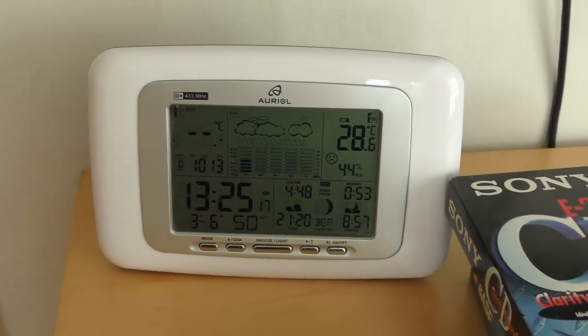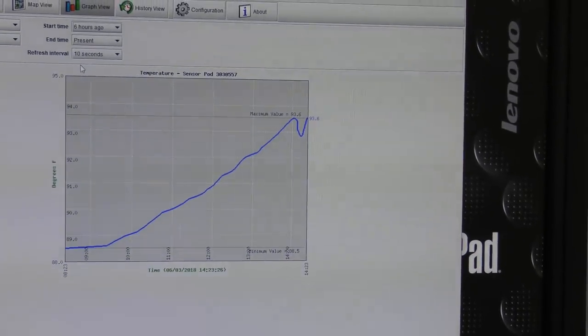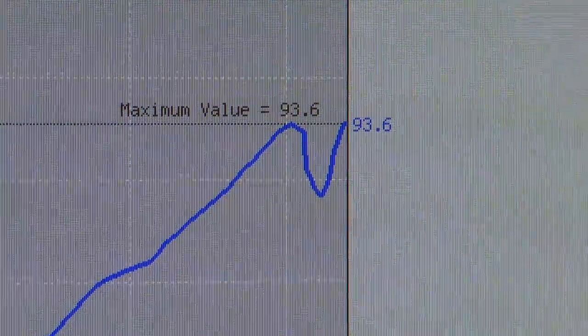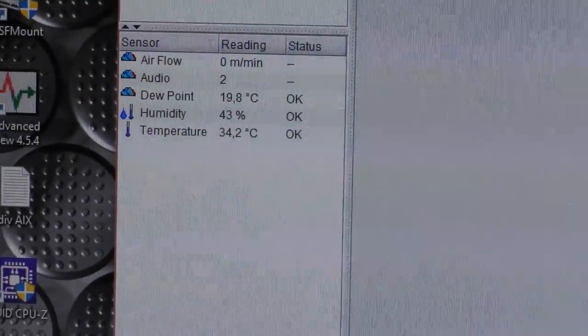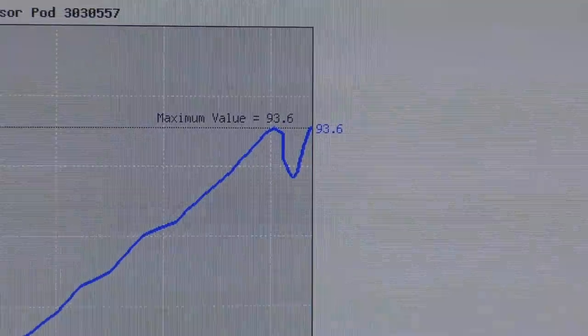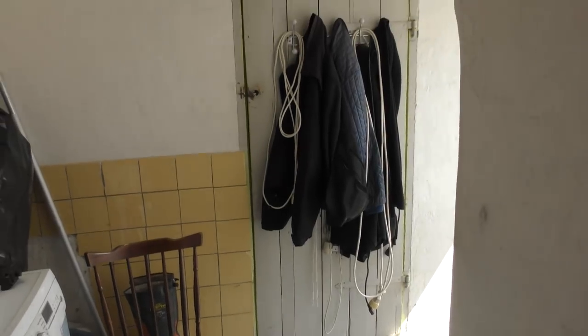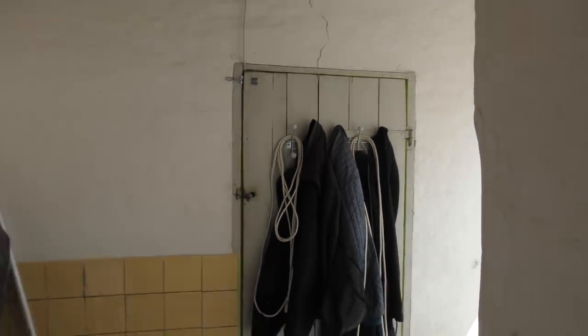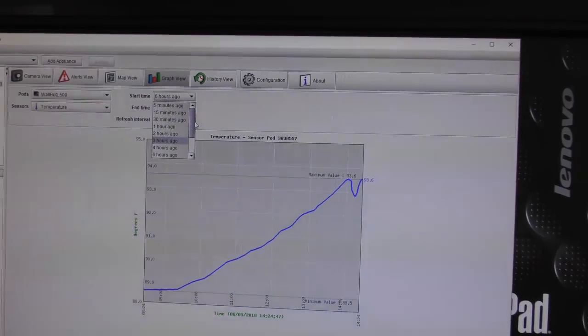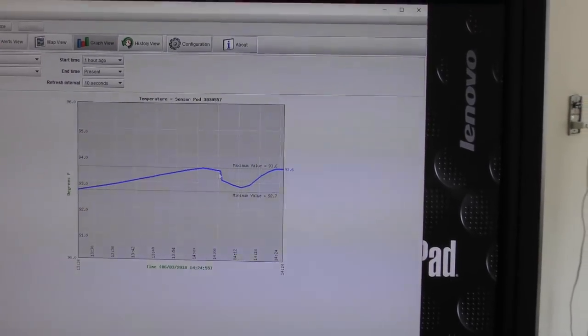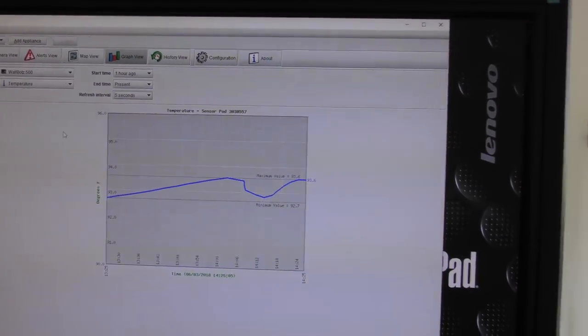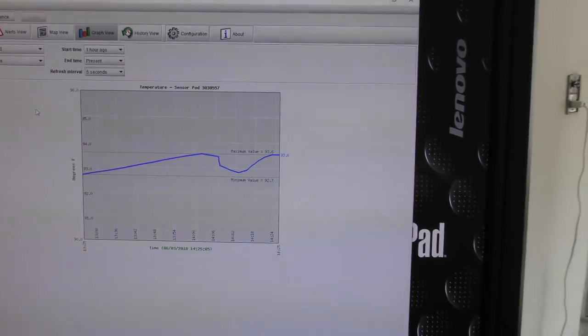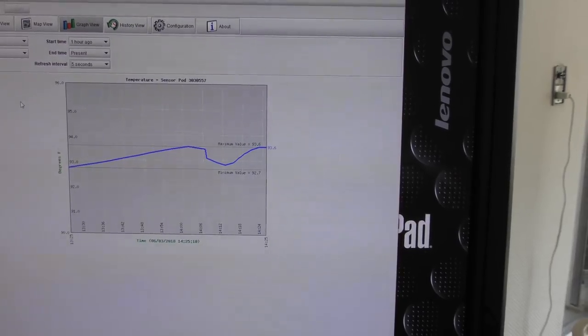Now the temperature is at exactly the same point as when we started. It tells it in Fahrenheit - I don't like this program. Over here it shows 34.2 degrees Celsius, which is apparently the same as 93.6 degrees Fahrenheit, and that is very warm. I'm closing the door to my data center now, in case the hot or cold air was just escaping. Let's see the last hour - the temperature didn't drop a whole lot when you zoom in that much. Let's get five second intervals and see what it does. It's really weird that it hit that same temperature and is just flat lying there.